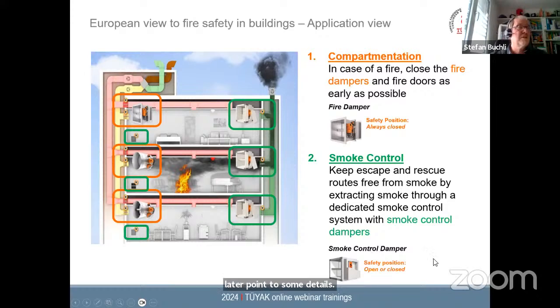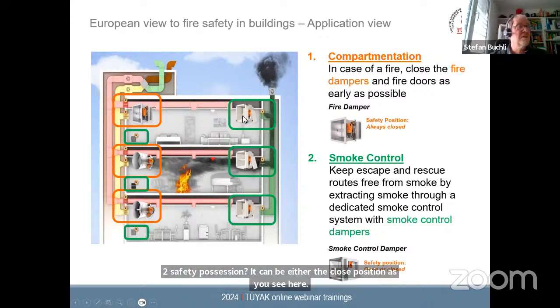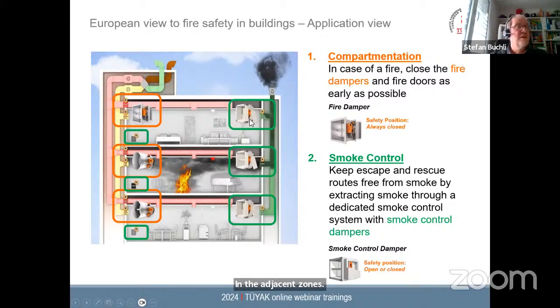What's special is that the smoke control dampers have two safety positions. It can be either the closed position, as you see here, in the zones adjacent to the fire zone. Here you hold the dampers in the closed position because you want to prevent smoke coming into these zones. And in the zone where the fire is, the safety position is the open position. Here you have a smoke extraction damper, and you also have a smoke extraction damper here, but this damper is for letting fresh air into the zone.